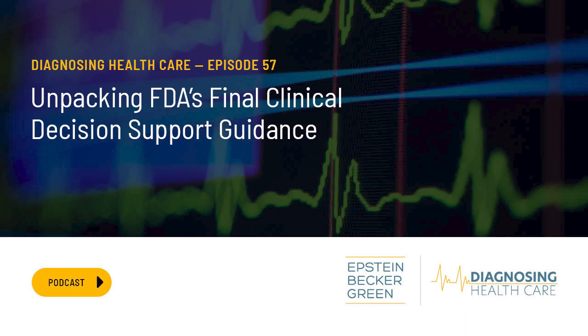Two years later, in 2016, the 21st Century Cures Act amended the Federal Food, Drug, and Cosmetic Act to formally carve out certain clinical decision support software functions from the statutory definition of medical device. Specifically, the statute sets forth 4 criteria that a product must meet in order to be excluded from the definition of a medical device, and products that are excluded from the definition would not be subject to FDA regulation and oversight.